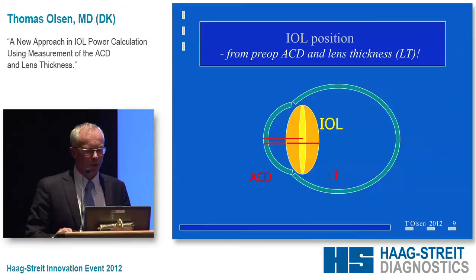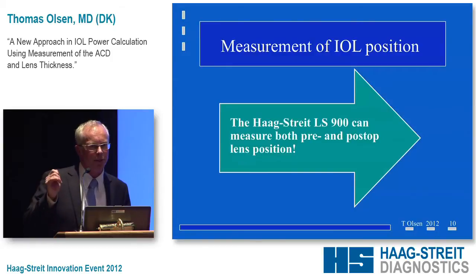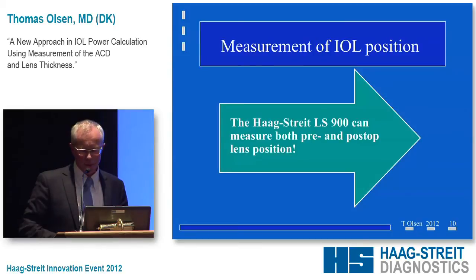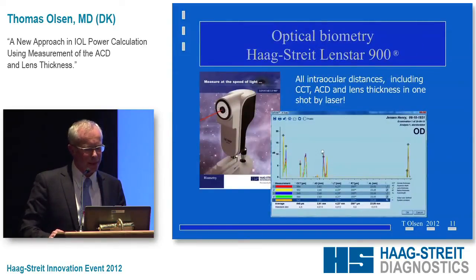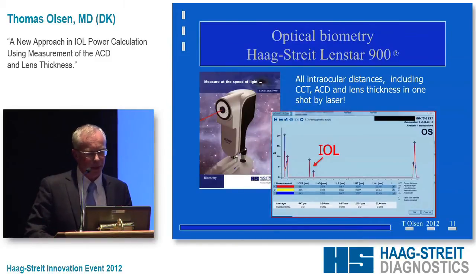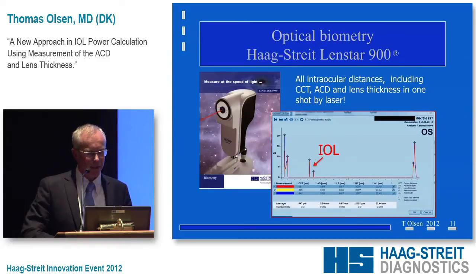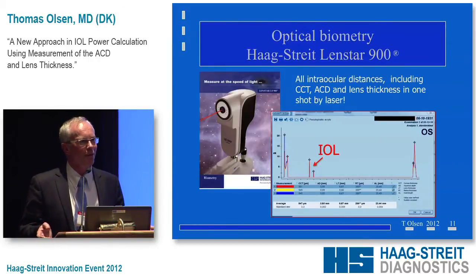If we measure the anterior segment structure — that is, the anterior chamber depth and the lens thickness — we can come up with a very nice correlation of the final position of the implant in that eye. With the Haag-Streit Lenstar 900, you can actually measure the IOL position with laser biometry, so it's very accurate. Lens thickness can be measured with high accuracy, and the final position of the implant comes up very nicely.